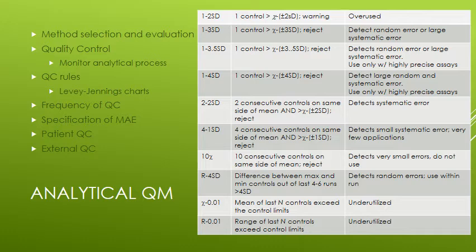In stage 3, you're going to finalize or establish the final QC ranges, right? The critical values, any delta checks, establish those within the computer system and train your personnel to use the new procedure and how it would work in your hospital. Then once that's done, you can complete and sign off on any procedures, you as the evaluating person, as well as anybody who's trained on it. And then you start notifying doctors, okay, finally we have something new that you can run on your patients. That's before you ever even run one patient specimen. You've done all this work, okay?